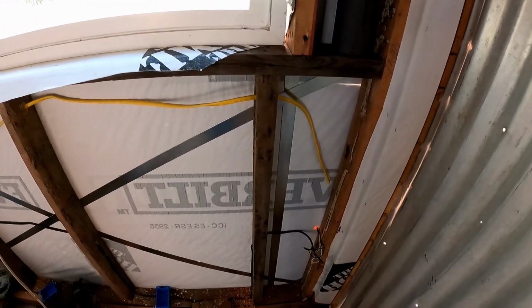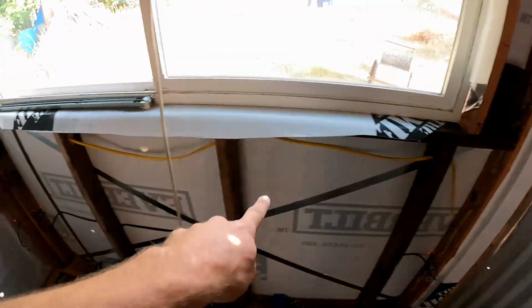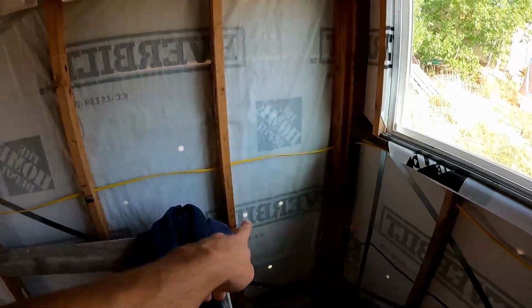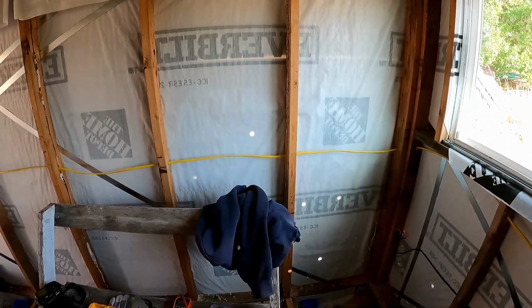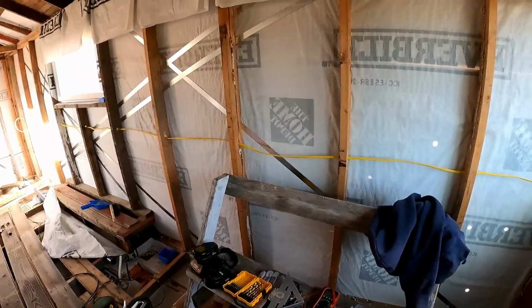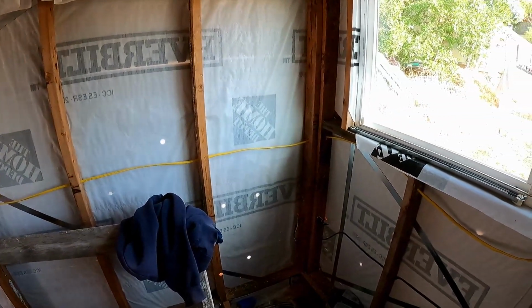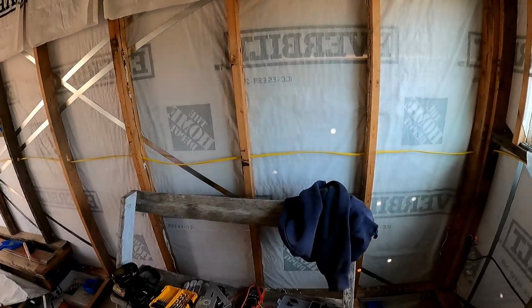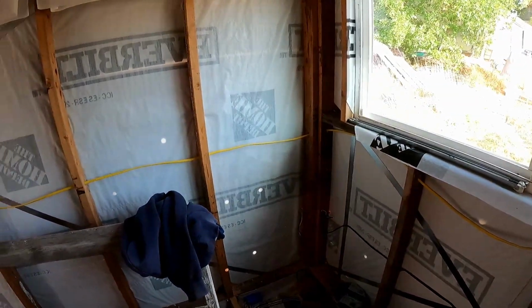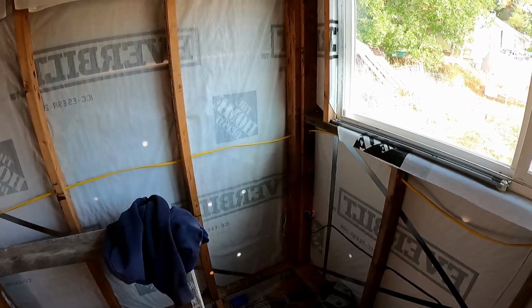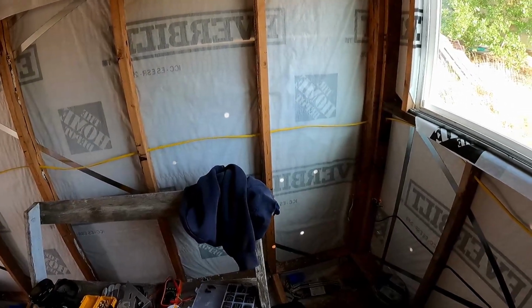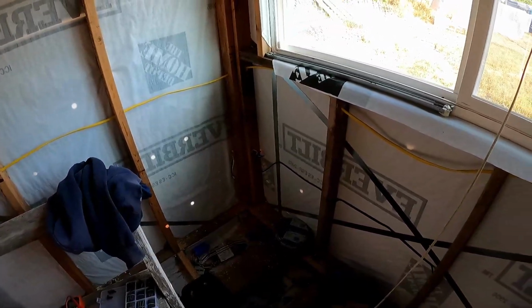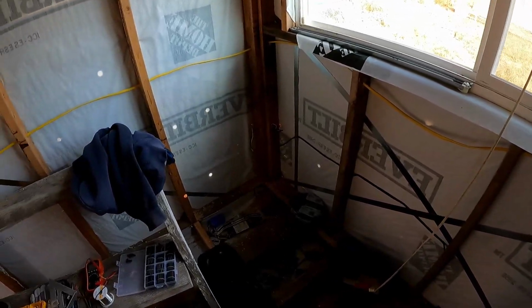I started stringing the wires here through holes that I've drilled. This is 12 gauge wire, and I'm running 20 amp circuits for outlets to the front here, so I have 2 outlets in the front, maybe one on the side. More outlets doesn't hurt. There's supposed to be a limit to how many outlets you put on a single run, but I think I'm well within that limit — it's like 7 or 10 or something like that. Honestly, the limits are somewhat arbitrary, so I'm not going to let them bother me too much.